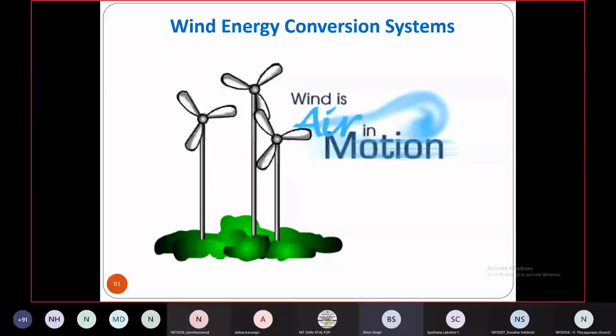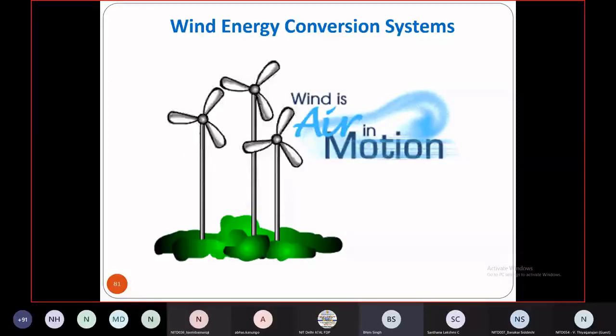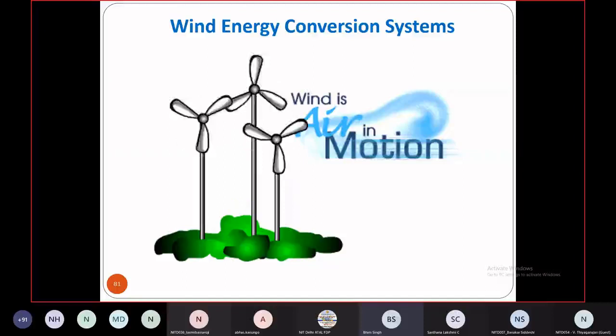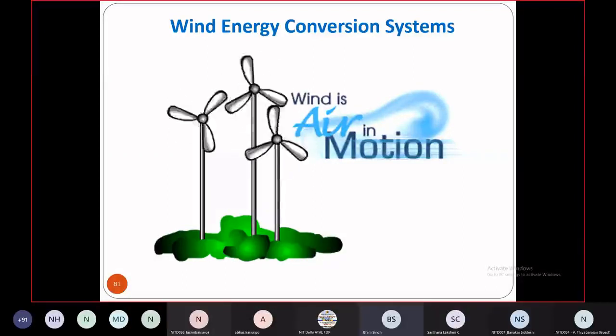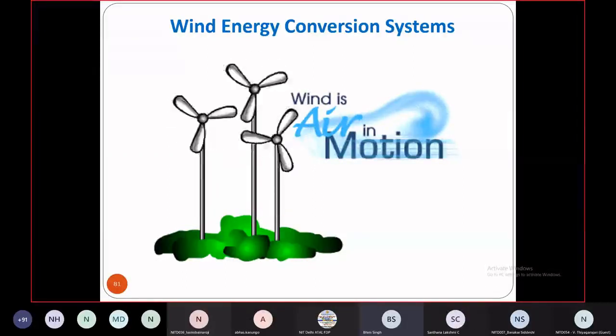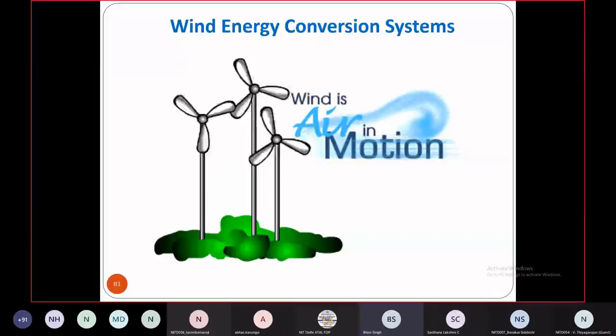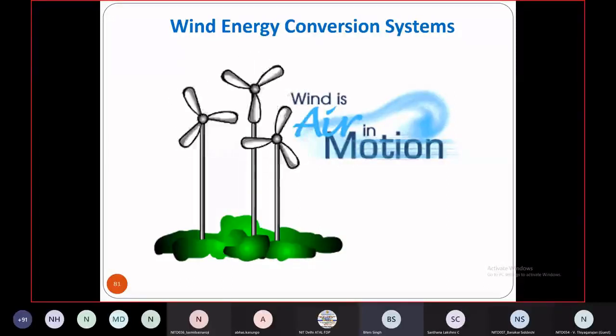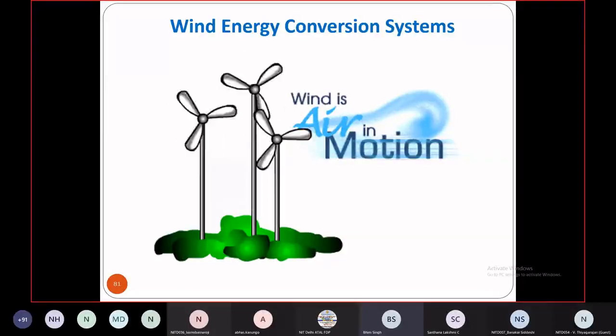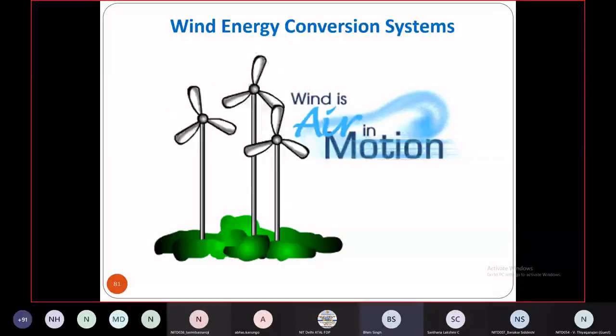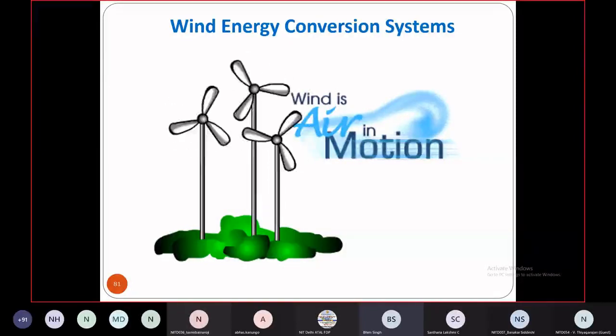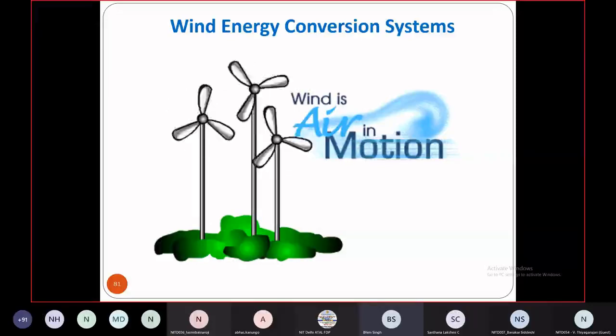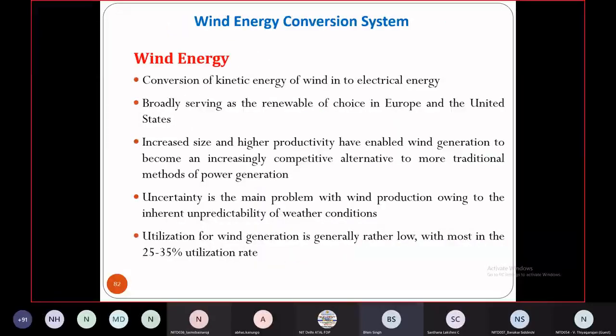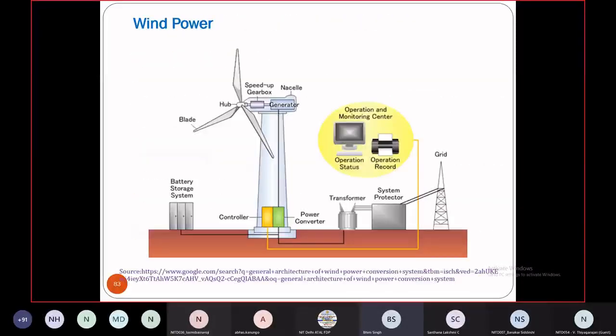In most of the cases, except the doubly fed induction generator, where the stator is directly connected to the grid, but the rotor is again connected through a double converter. So around 30 to 35% of the power is processed through the rotor converter, the double converter, but the other power is directly fed to the grid. And you can take the benefit of operating at variable speed and getting again 50% more energy generation in that case also.